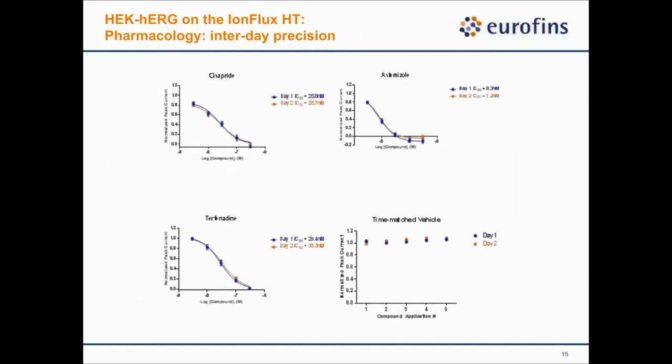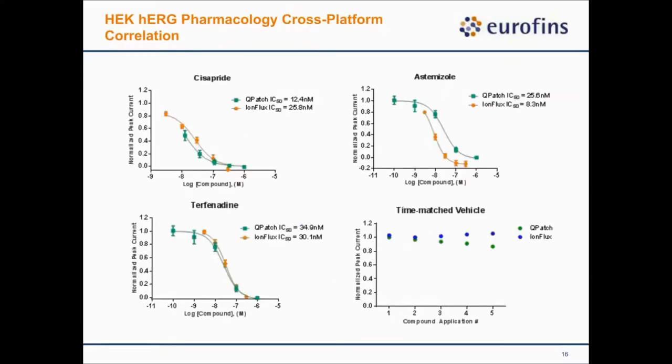In the next set of experiments, we looked at inter-day precision to test assay robustness. We picked three compounds — cisapride, Astemizole, terfenadine — and time-matched vehicle control and tested those on two different days. Between day one and day two, the IC50 values are very close to each other, showing that our hERG assay on the IonFlux is very robust. We then compared IC50 values of reference compounds between Qpatch and IonFlux. They agree with each other, and the time-matched vehicle control shows very good minimal current rundown.